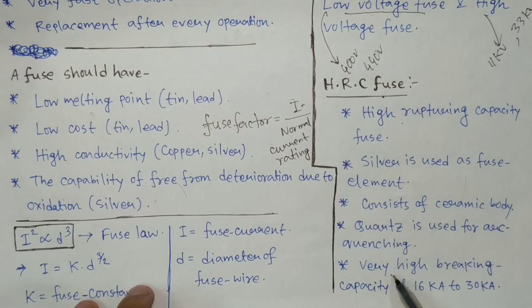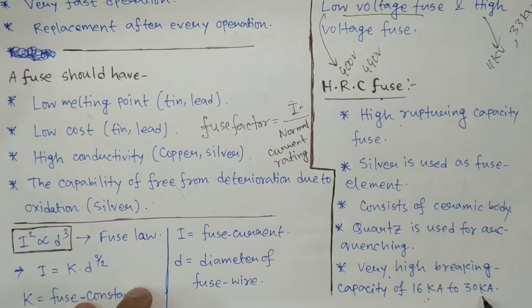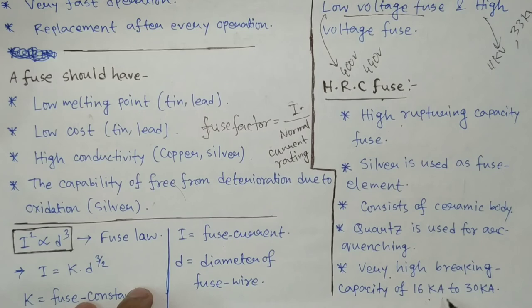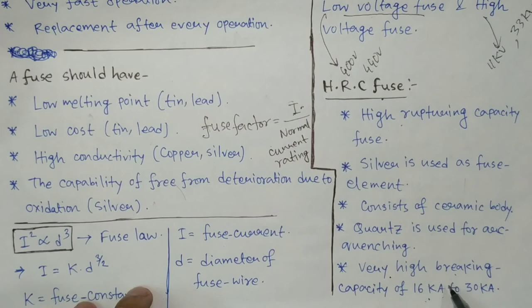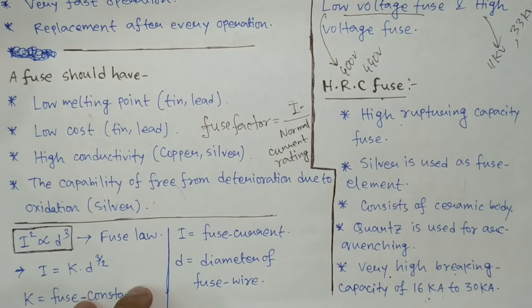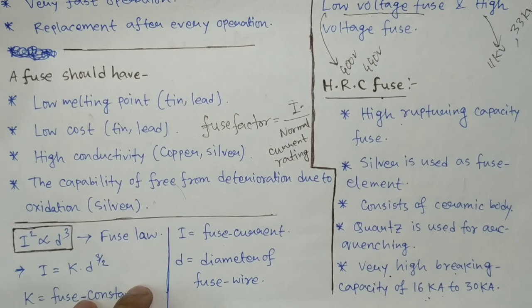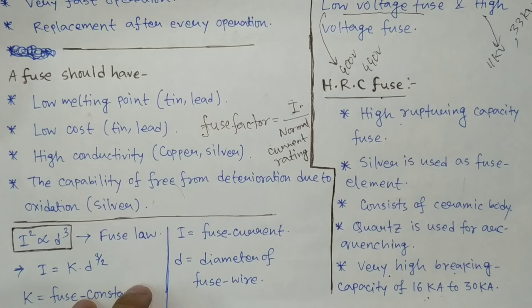HRC fuse has breaking capacity around 16 kilo amps to 30 kilo amps. No other fuse has as high breaking capacity as HRC fuse, and that is why HRC fuse is widely used. Breaking capacity means it is that RMS value of current at which the fuse can successfully break the circuit by melting without damaging the surrounding.